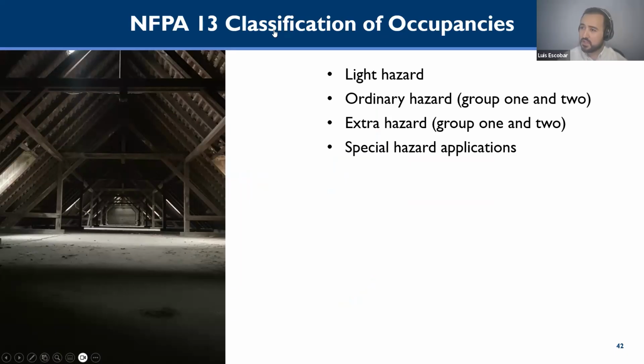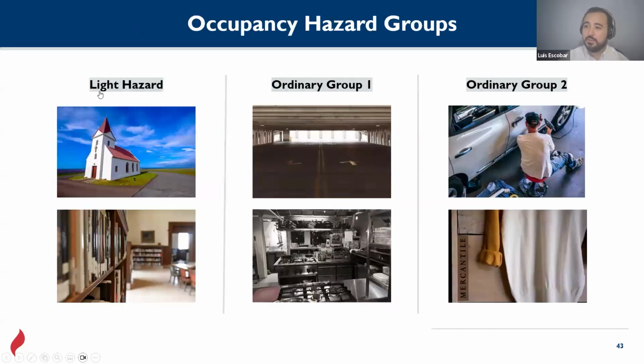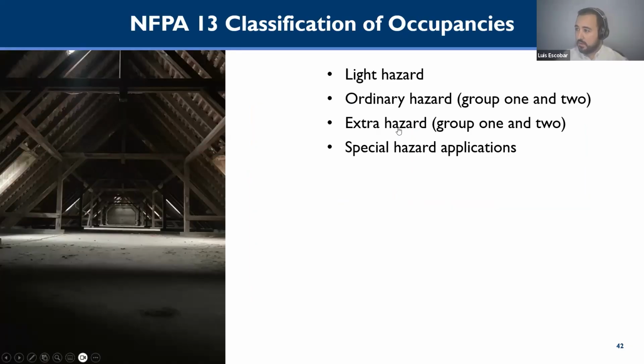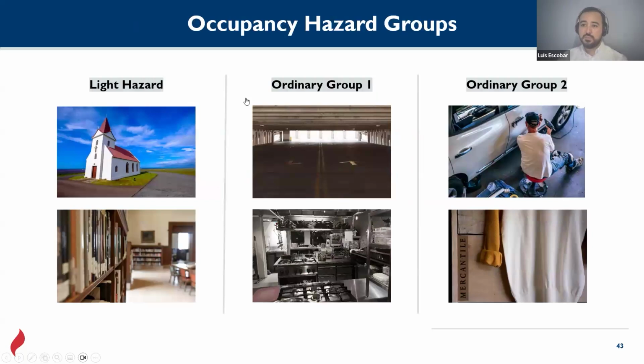Occupancies are classified in NFPA 13 as light hazard, ordinary hazard, extra hazard, and special hazard applications. We'll go over those. Light hazard occupancies. The difference between these is the amount of heat released by the combustibles in the occupancy. For example, with light hazard, the fire sprinkler system won't be too complex to extinguish the fire. Smaller pipes are needed, a small sprinkler head, no storage.